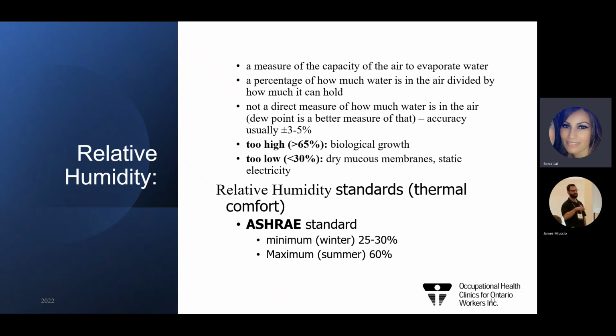With regards to relative humidity, what's important to note is if your relative humidity is too high, such as greater than 65%, you will enable biological growth—mold, mildew, that type of thing—so you want to make sure you're below that level. And if you're too low, below 30 or below 20%, you're going to have folks who wear contact lenses, for example, have dry eyes and irritation, dry mucous membranes, more static electricity, etc. So you want to make sure you're in a happy range.